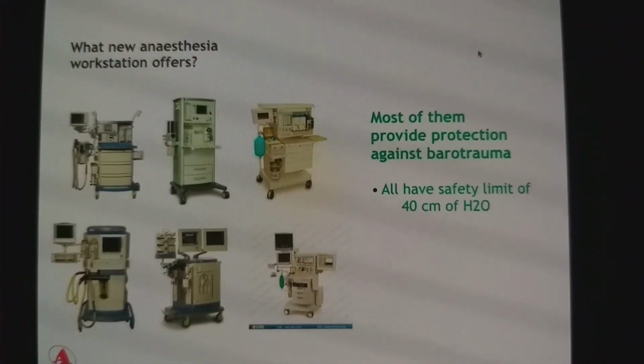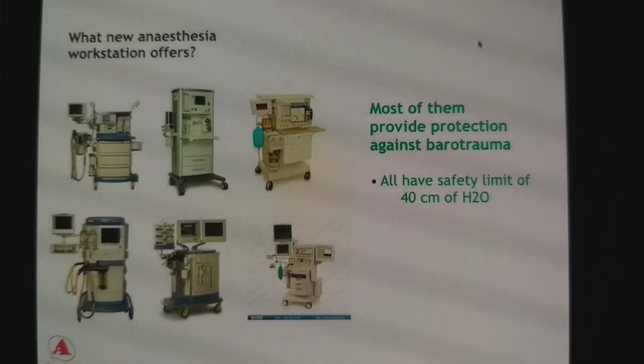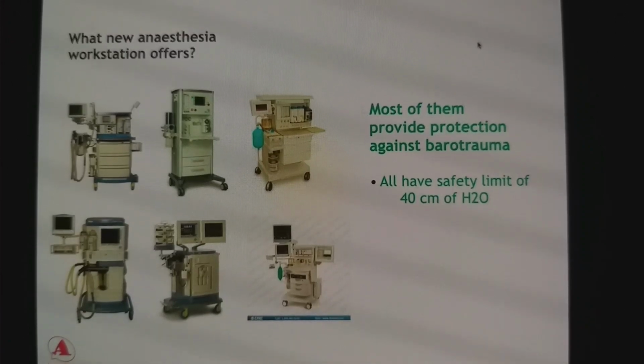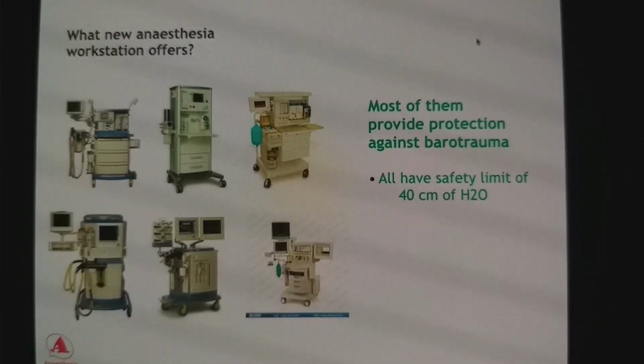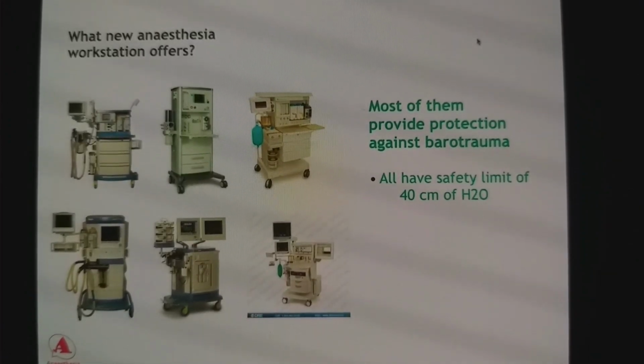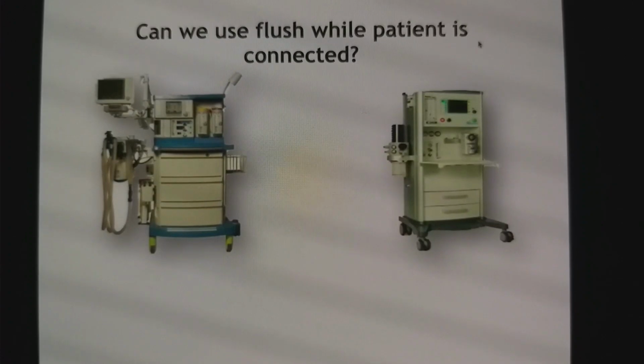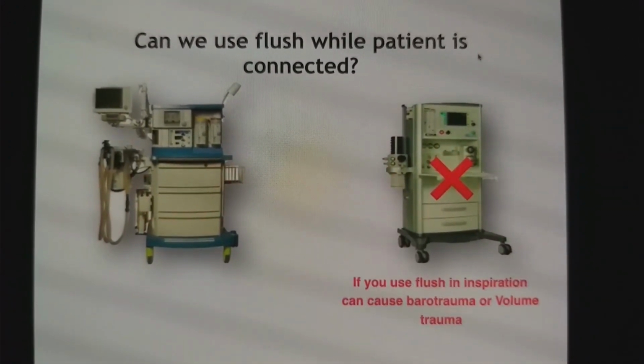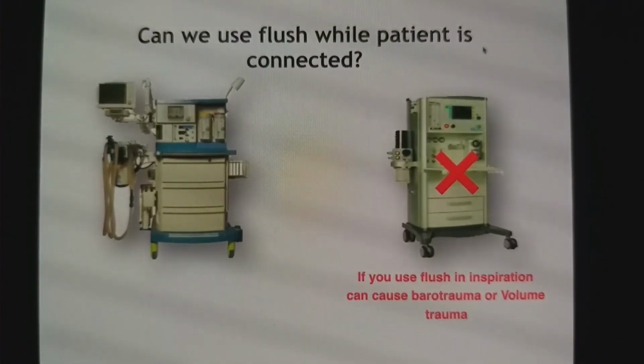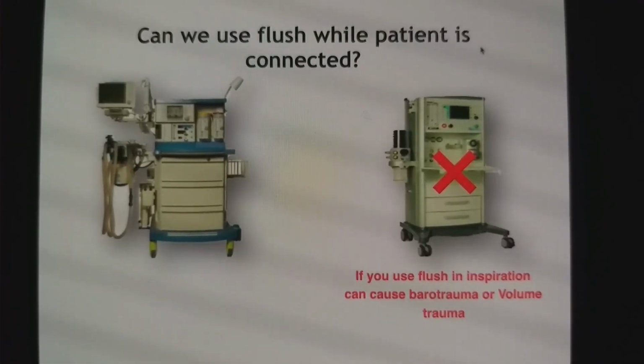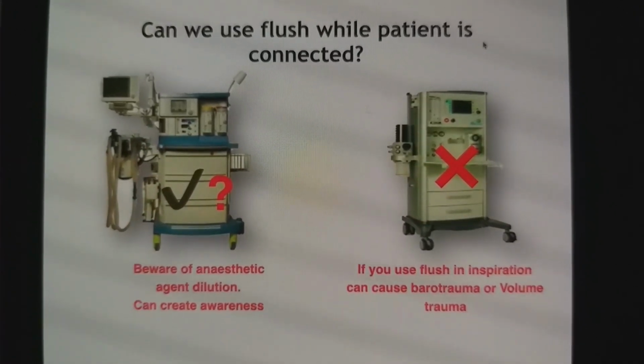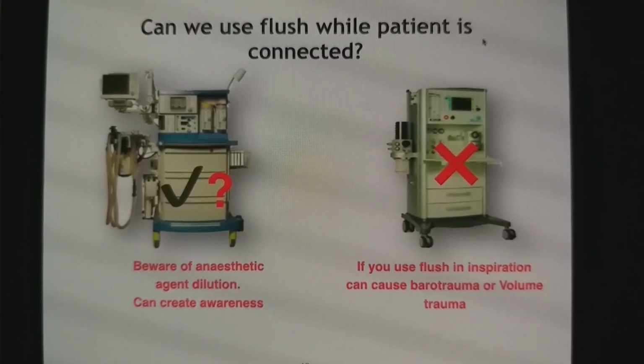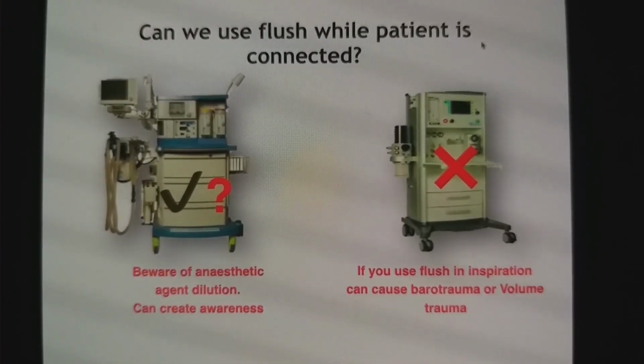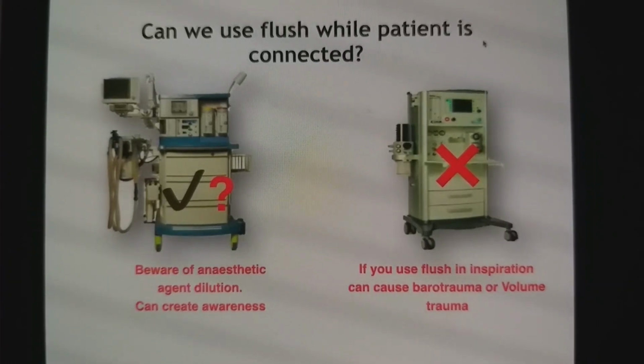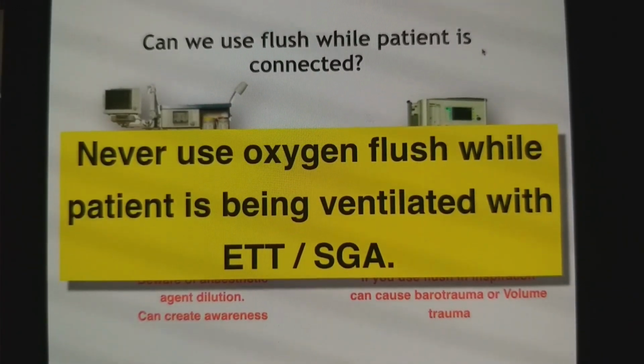Fortunately, majority of the machines will prevent barotrauma by keeping a safety upper limit of 40 centimeters of H2O on all anesthesia machines. Beyond that, it will not deliver tidal volume. But imagine that is happening to a pediatric patient. Imagine that can also cause volume trauma. So can we use flush while patient is connected? Absolutely no. In case of bellows anesthesia machine, it can cause barotrauma, it can cause volume trauma. In case of Draeger machine, you can do it without doing any harm to the patient. But again, you have to beware of anesthetic agent dilution. Your patient may develop awareness if you press flush. So essentially, you should never use oxygen flush while patient is being ventilated with endotracheal tube or supraglottic airway.